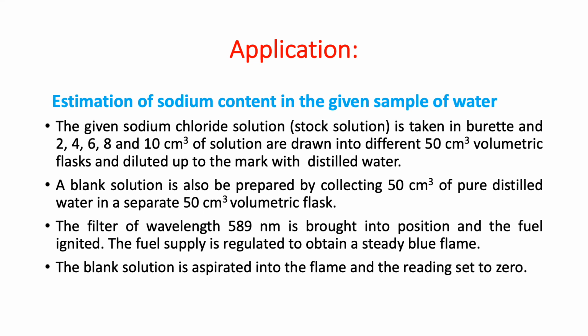And you have to set the filter before aspirating your distilled water. I forgot to mention this. You have to set 589 nanometer in the filter. This is for sodium. This wavelength varies depending upon the element you use. You will have some filters.